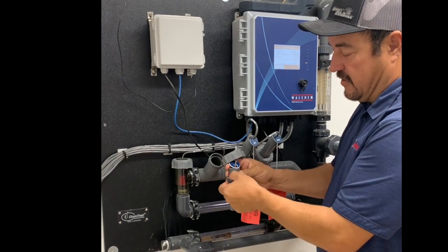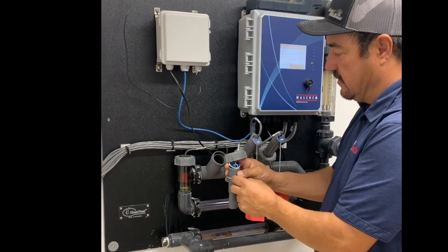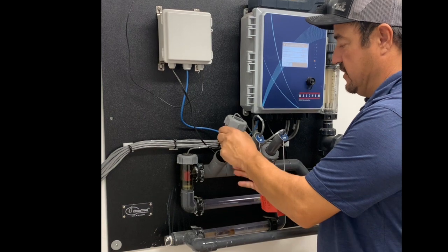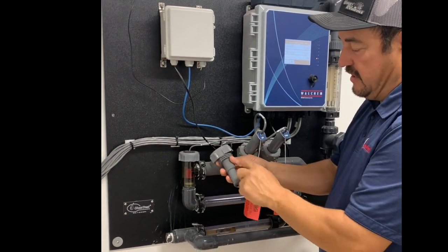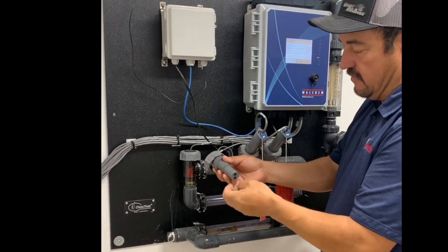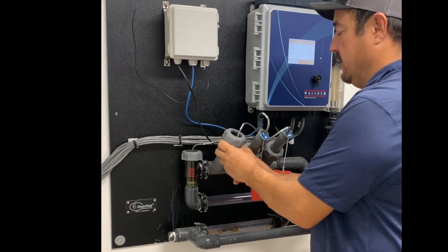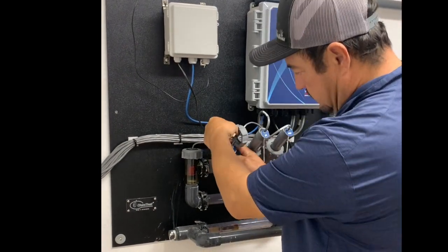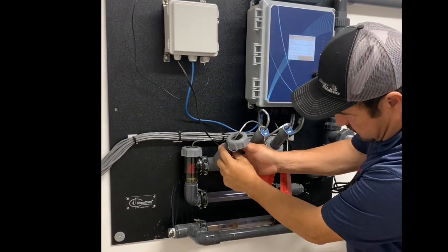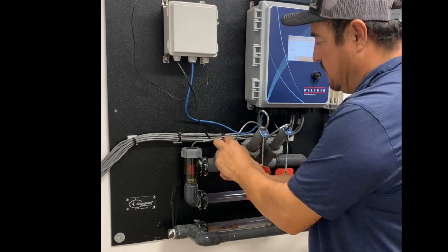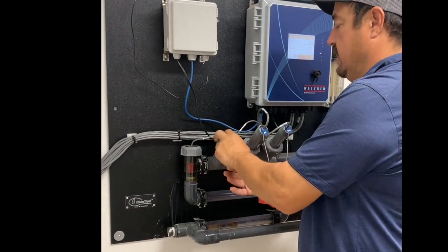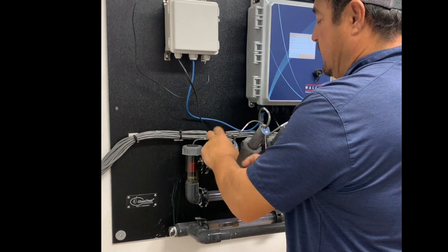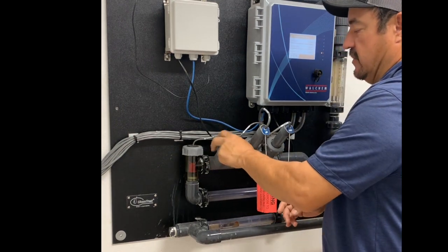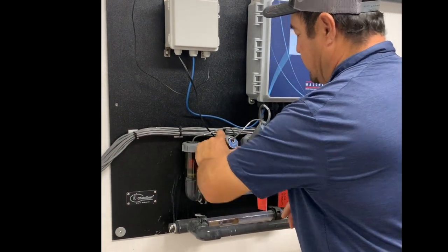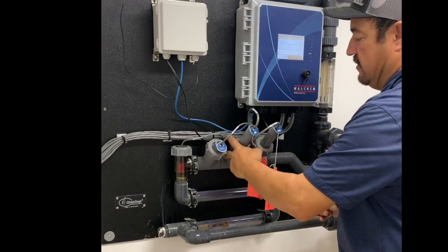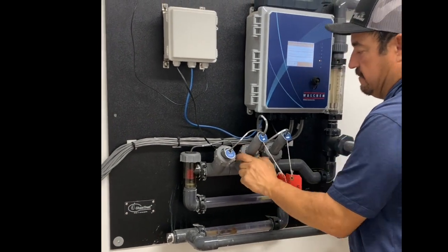On the conductivity probe, on the Walchem probes, most of them have a little line up on them, on the probe itself. We've seen it's clean, we know it's clean, we've rinsed it off, we've wiped it off, and put it back in. Line up the actual fitting there and screw it back in. Now we know that conductivity probe's clean, so now we could go through and do our calibration. I'm going to show you something really quick too on the pH probe.